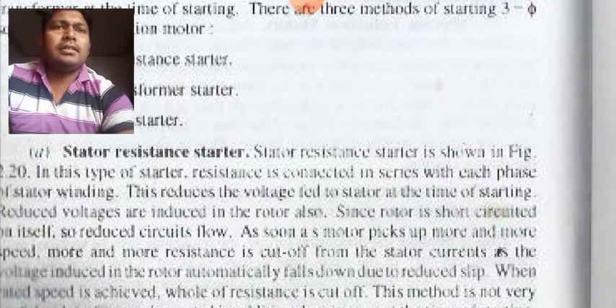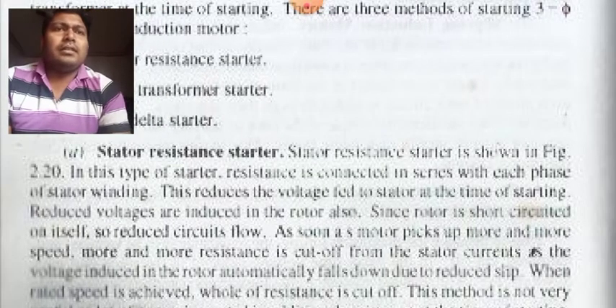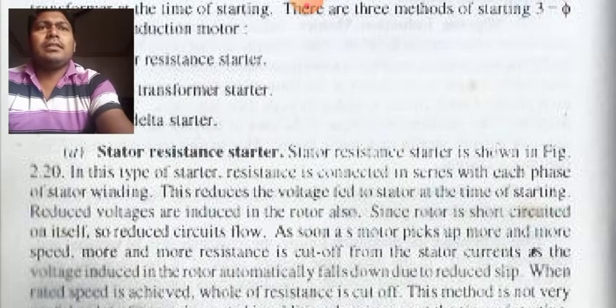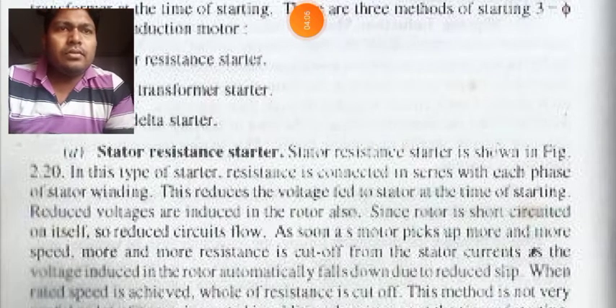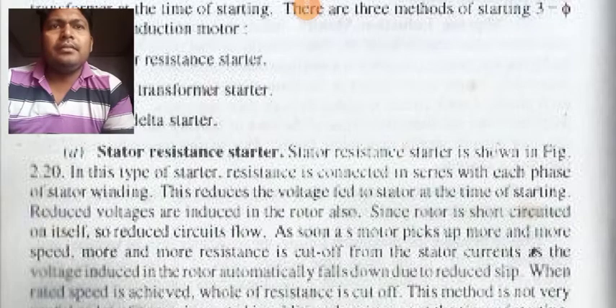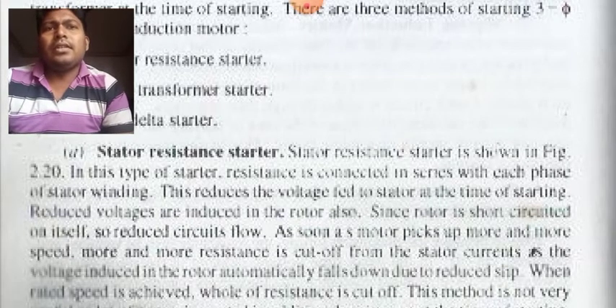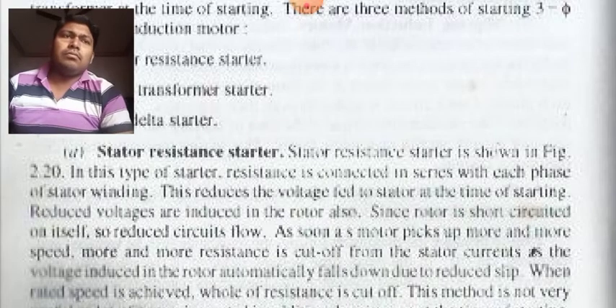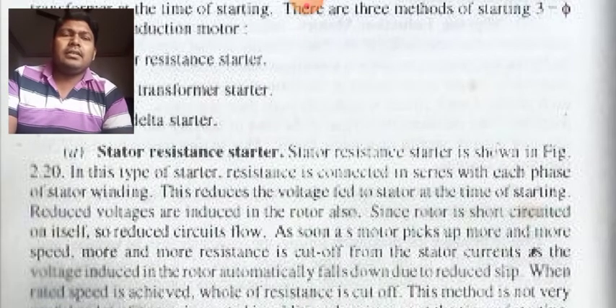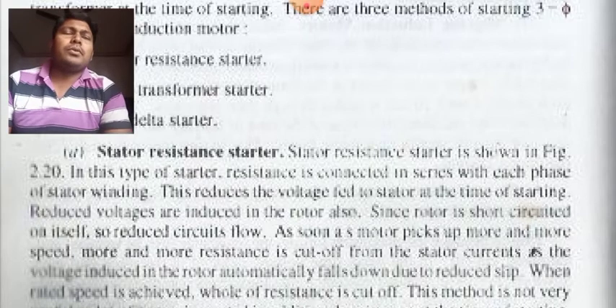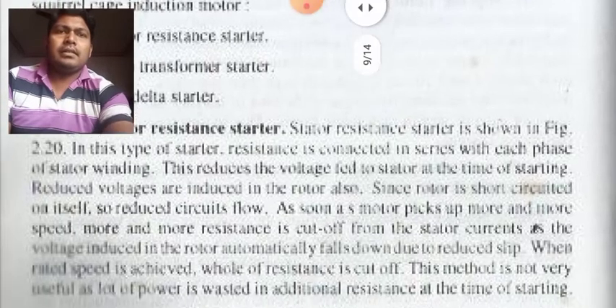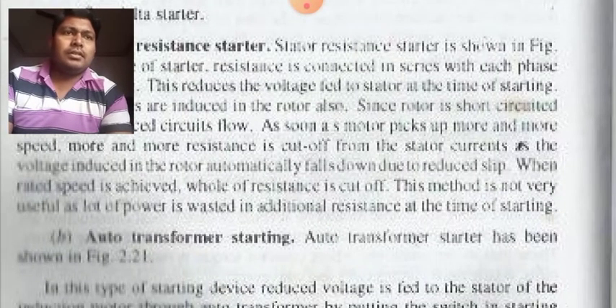The stator resistance starter is as in the diagram. In this type of starter, resistance is connected in series with each phase. This reduces the voltage fed to the stator at the time of starting. Reduced voltage is induced in the rotor also. Since the rotor is short circuited on itself, reduced current flows. As soon as the rotor picks up more and more speed, more and more resistance is cut off from the stator circuit, as the induced voltage automatically falls down due to slip. When rated speed is achieved, the whole of the resistance is cut off. This method is not very useful, as a lot of power is wasted in the additional resistance at the time of starting.